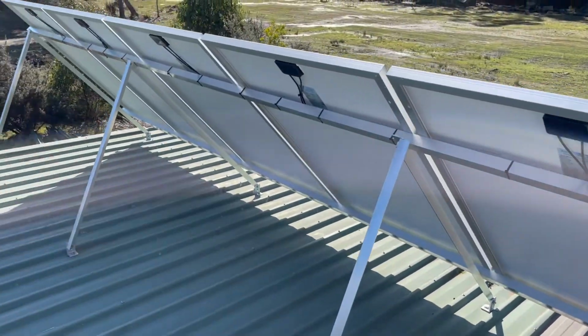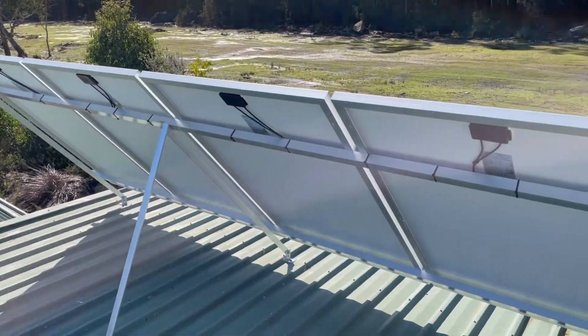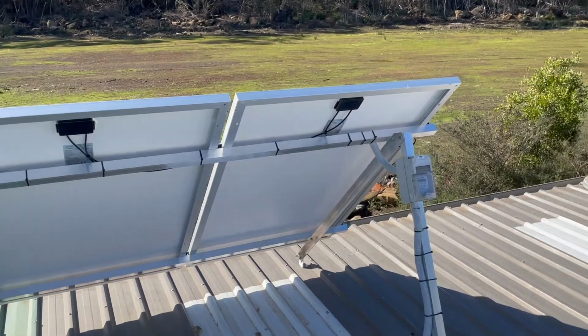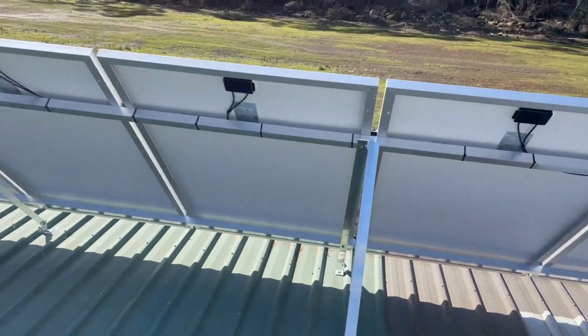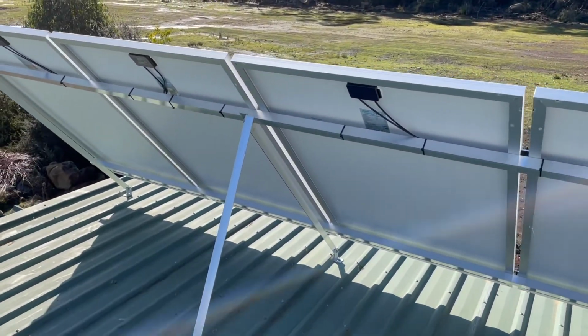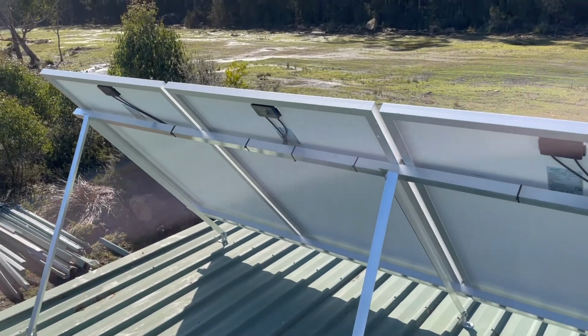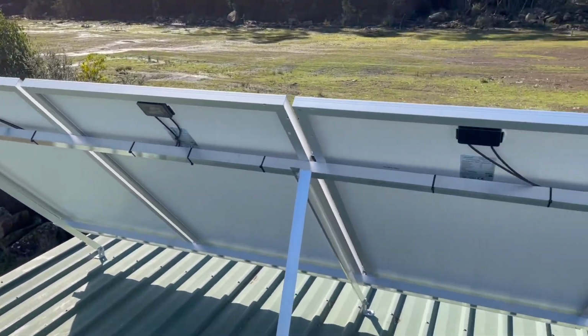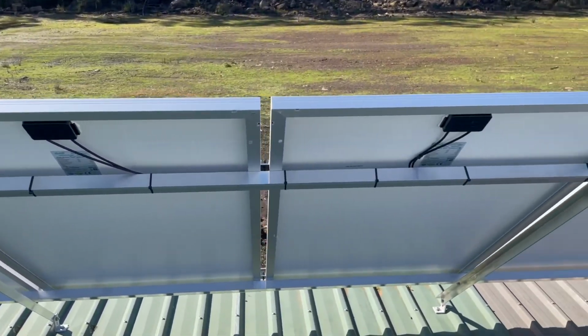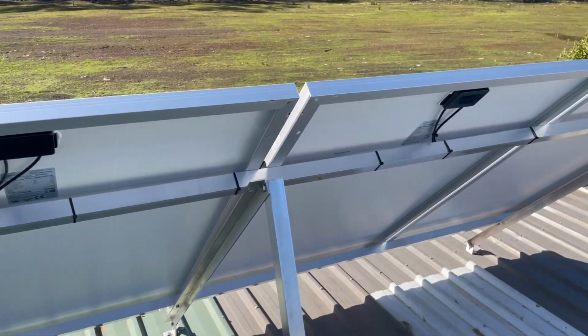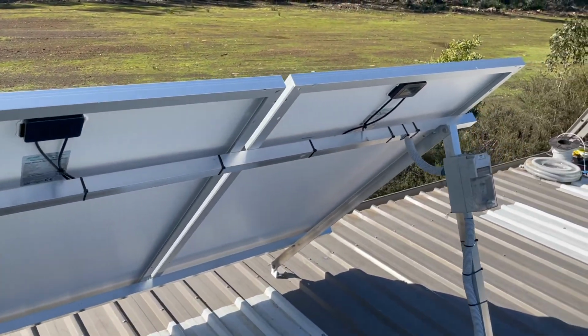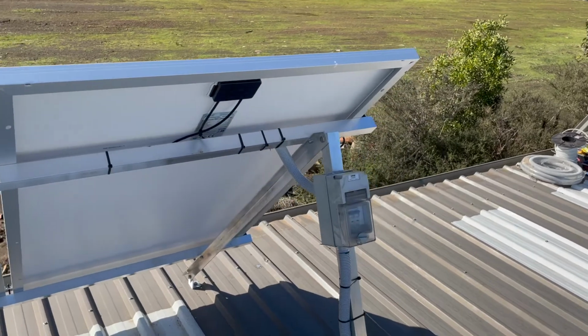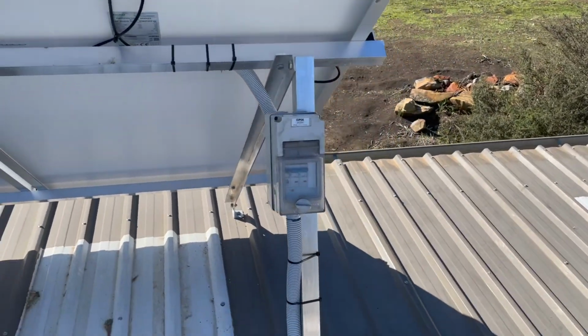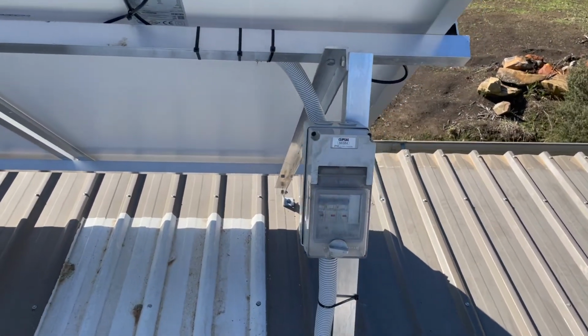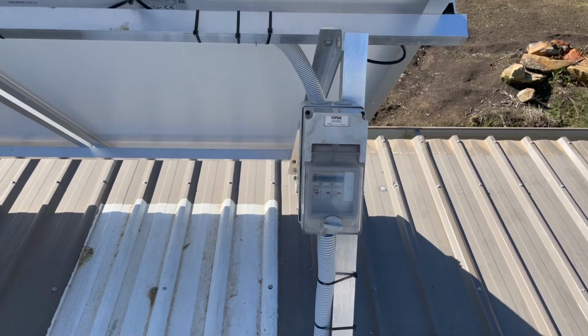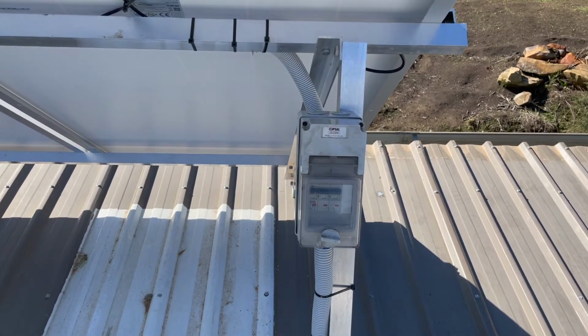I've got three pairs of solar panels wired together in series. I've got the positive and negative leads coming out of those, crimped to wire and heat shrunk on, following the channel down that supports the array underneath it, out of the weather. It's held in position with cable ties, as you can see. It comes down to the solar array disconnect, which I've mounted on a strut out of the weather. The solar array disconnect simply allows me to turn the solar array off and on from the roof.